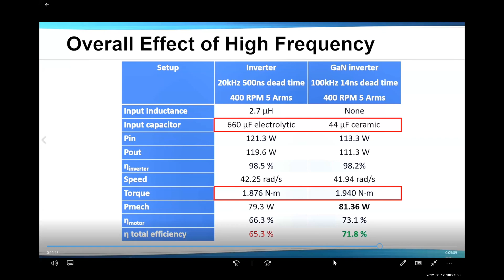If you look here, 98.5, 98.2, what really changes is that by giving a better voltage signal, which is more sinusoidal, to the motor, the motor is acting more like an ideal motor, and so it's getting higher torque per the same current. And at the end of the day, what is really increasing is the mechanical power. Even though the speed is the same, the torque is increased, and the mechanical power is higher. So then if you do the total overall efficiency, considering input electric power, output electric power, and then output mechanical power, you get an increase in the efficiency of the overall system.